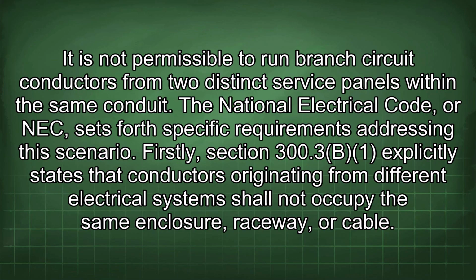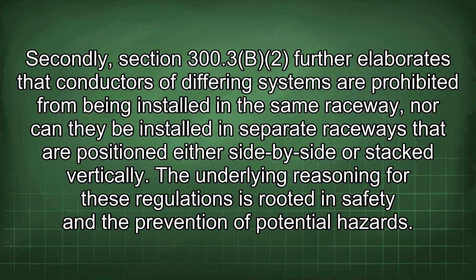It is not permissible to run branch circuit conductors from two distinct service panels within the same conduit. The National Electrical Code, or NEC, sets forth specific requirements addressing this scenario. Firstly, Section 300.3(B)(1) explicitly states that conductors originating from different electrical systems shall not occupy the same enclosure, raceway, or cable. Secondly, Section 300.3(B)(2) further elaborates that conductors of differing systems are prohibited from being installed in the same raceway, nor can they be installed in separate raceways that are positioned either side by side or stacked vertically.